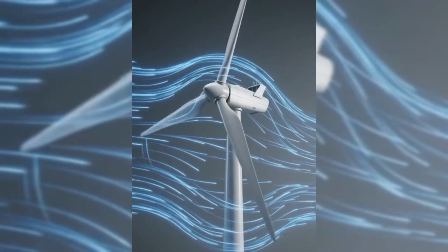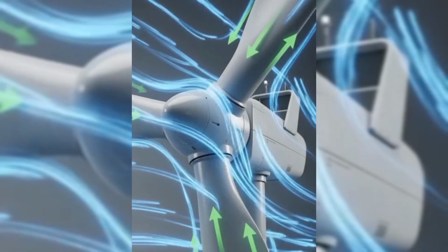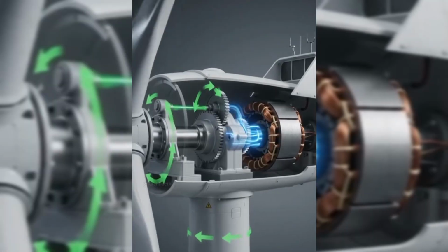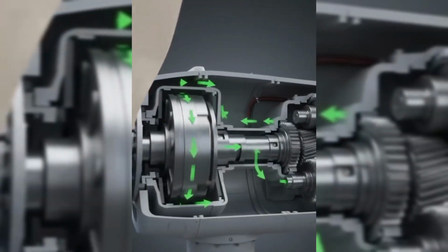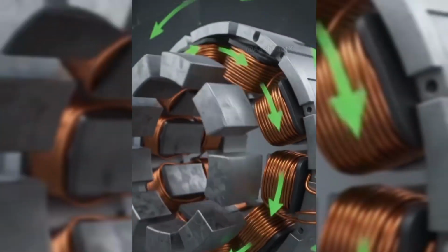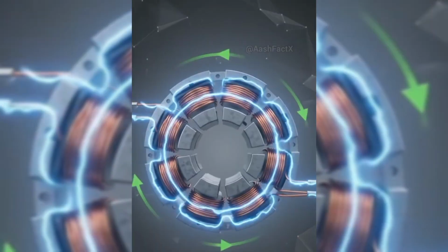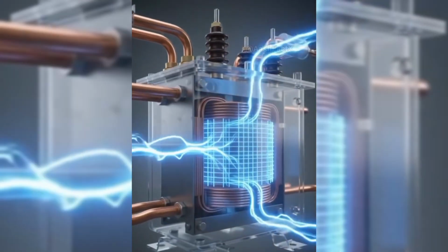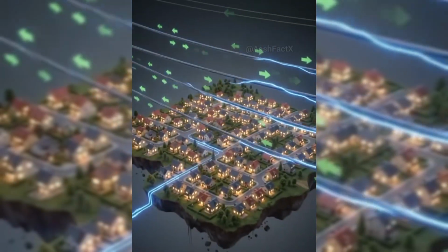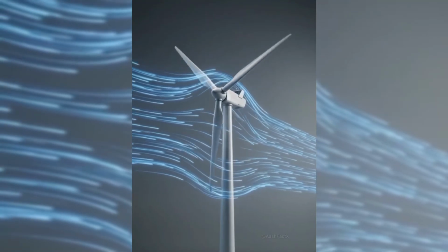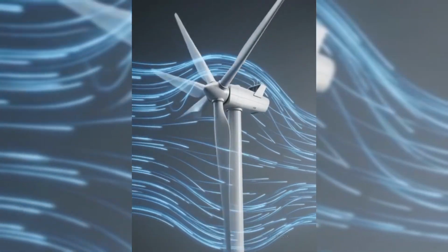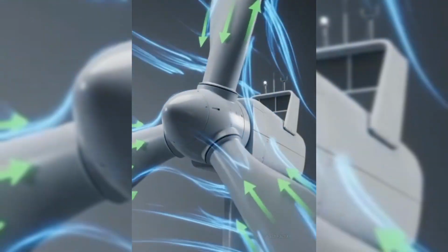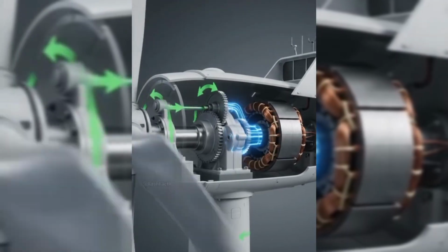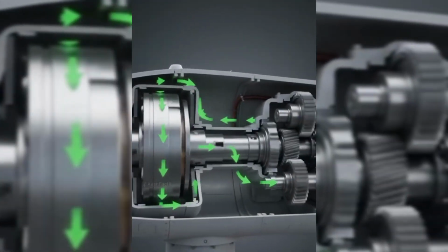Modern wind turbines typically feature a step-up transformer located either inside the base of the tower or in a small housing right next to it. The transformer operates on the principle of electromagnetic induction. It consists of two separate coils of wire wound around a shared iron core. The primary coil receives the low-voltage electricity coming from the generator, while the secondary coil outputs electricity at a significantly higher voltage. By having many more turns of wire on the secondary coil than on the primary coil, the transformer steps up the voltage, increasing it to thousands or tens of thousands of volts, while proportionally decreasing the current.